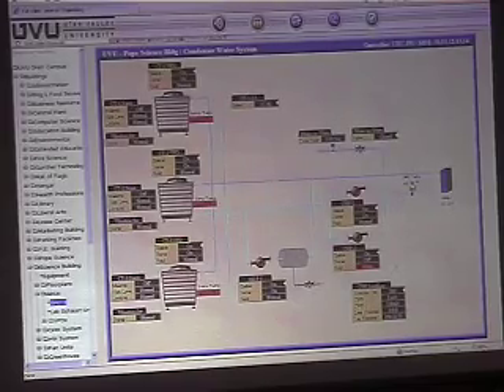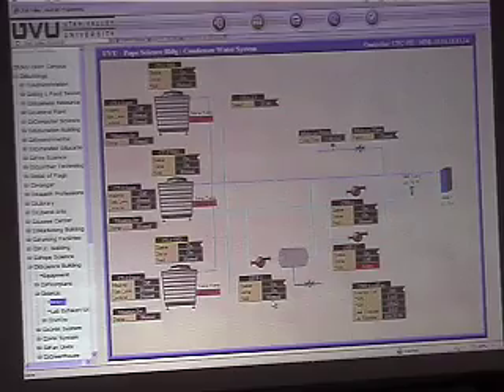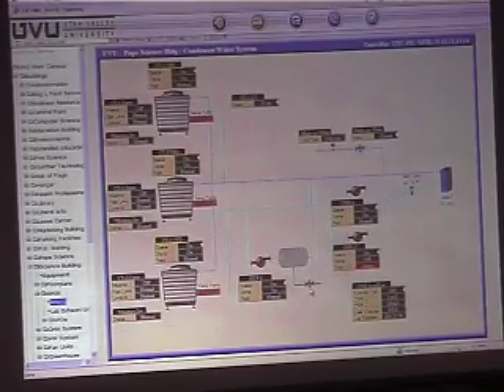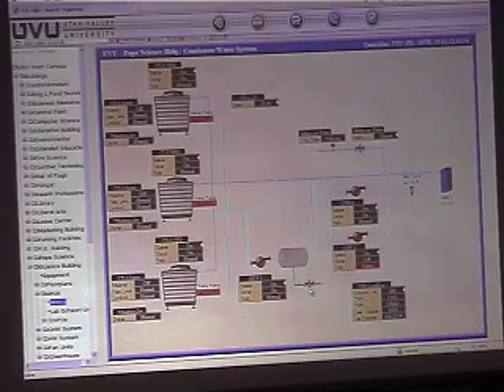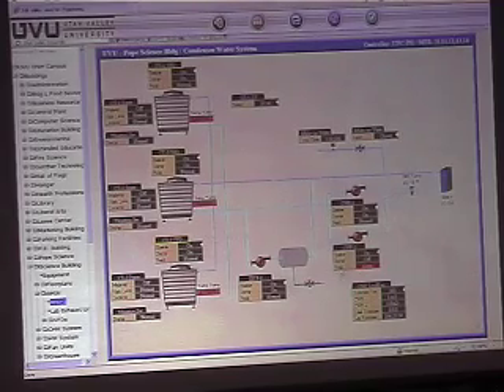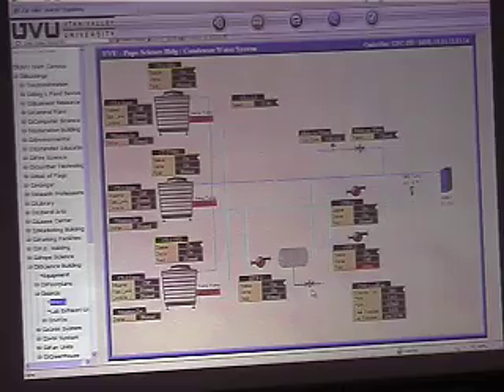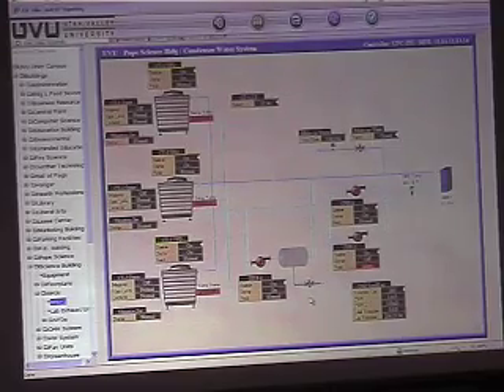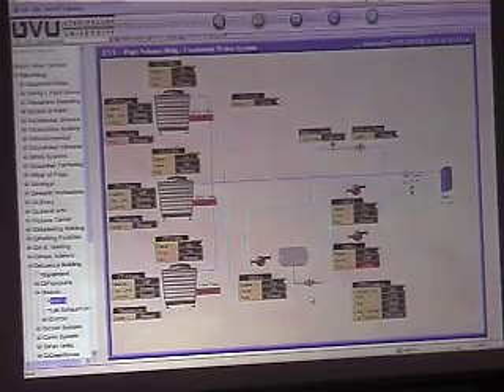Indication of your temperature here, of what the temperature is going through the coil. There's a solid separator up there that runs whenever these pumps are running, to filter that water through the solid separator. And then once a day, if these condenser pumps have been running at all during the day, at the end of the day, this valve will open up for 30 seconds and blow down that filter.